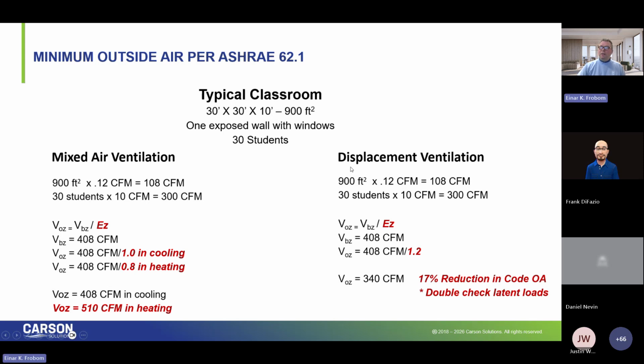Conversely, if I look at doing this design with our displacement induction ventilation, do the same math on the students and the staff, or the square footage, divide by a bigger denominator, which results in a smaller answer. Now I do need to double check with the reduction of outside air. Do I meet my latent load? Sometimes I don't. So let's say I have to add 20 CFM.